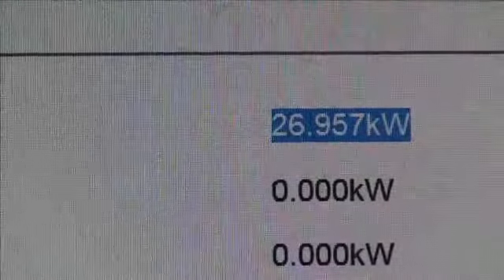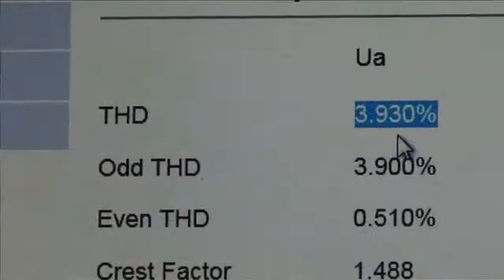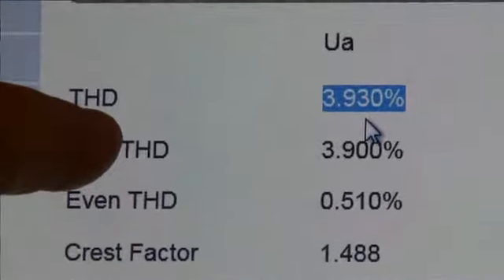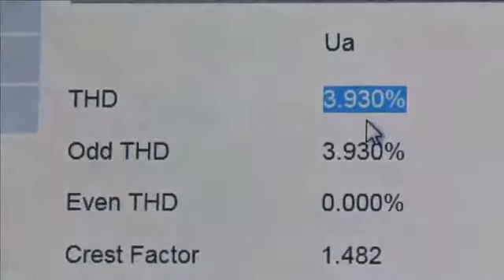The total harmonic distortion measures the quality of the power. Anything below 20% is okay. In the U.S., we get about 8% off the street. We are at 3.93%, which is exceptional quality.